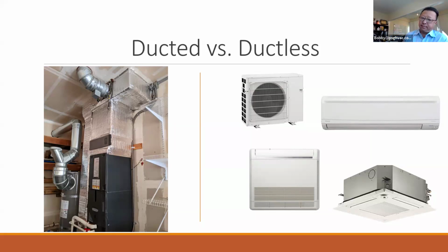But ducted versus ductless. On the left-hand side, that's a traditional system. Like I mentioned earlier, the variable capacity heat pump manufacturers, most of which make a furnace style indoor unit, or it can be mounted, in this case, in the garage. And then on the right-hand side, you have the ductless units. The world's most commonly used form of residential air conditioning is what's on the right-hand side, a high wall mini split. And then we also have various cassette styles, under ceiling, which is on the left, and which can also be mounted on the wall. And above that, it's going to be a traditional suitcase style condensing unit.